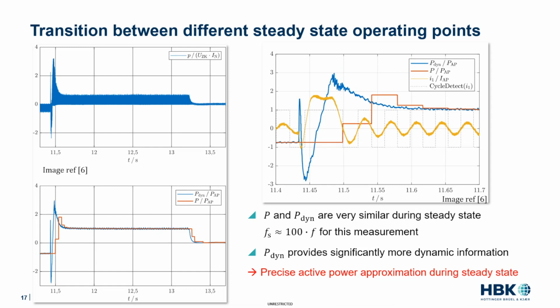And this was done by use of a load machine. So the device under test was speed controlled with constant speed, and the mechanically connected load machine was used to generate a load torque. By changing, for a constant speed, not only the value but also the sign of the load torque, we can go from generator to motor operation. And this is done here in this measurement.